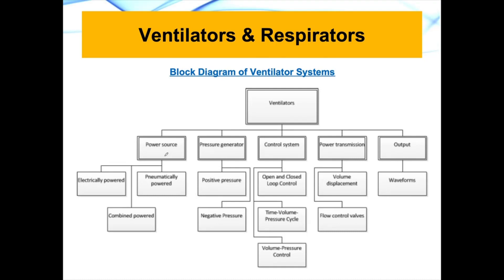The first thing is the power source, which can be used to classify a ventilator. We have electrically powered, pneumatically powered, or a combination of both. Pneumatically powered ventilators use pressure to move parts of the mechanical system rather than an electrical system.